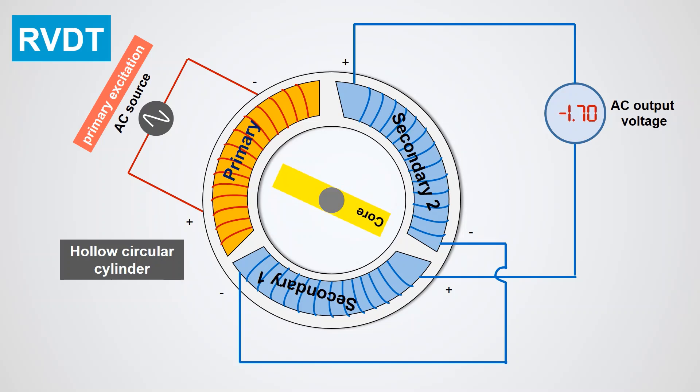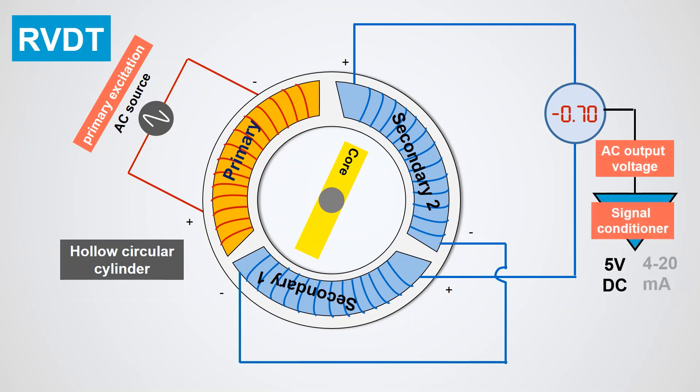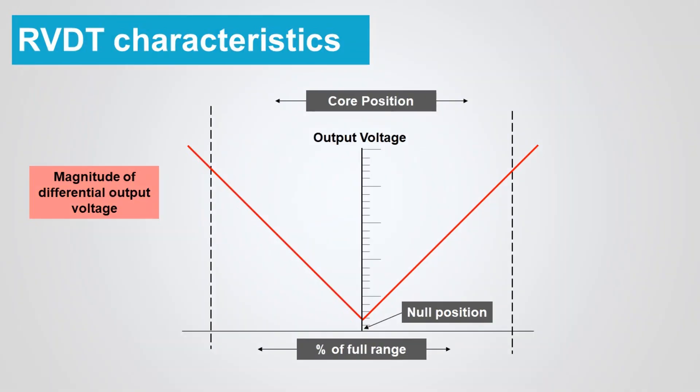A signal conditioning circuit is housed inside the RVDT structure and is required to convert the output to either 5V DC or 4 to 20mA, whichever format is compatible with your data acquisition. The magnitude of the differential output voltage varies with the core position. The value of output voltage at maximum core displacement from null depends upon the amplitude of the primary excitation voltage and the sensitivity factor of the particular RVDT.